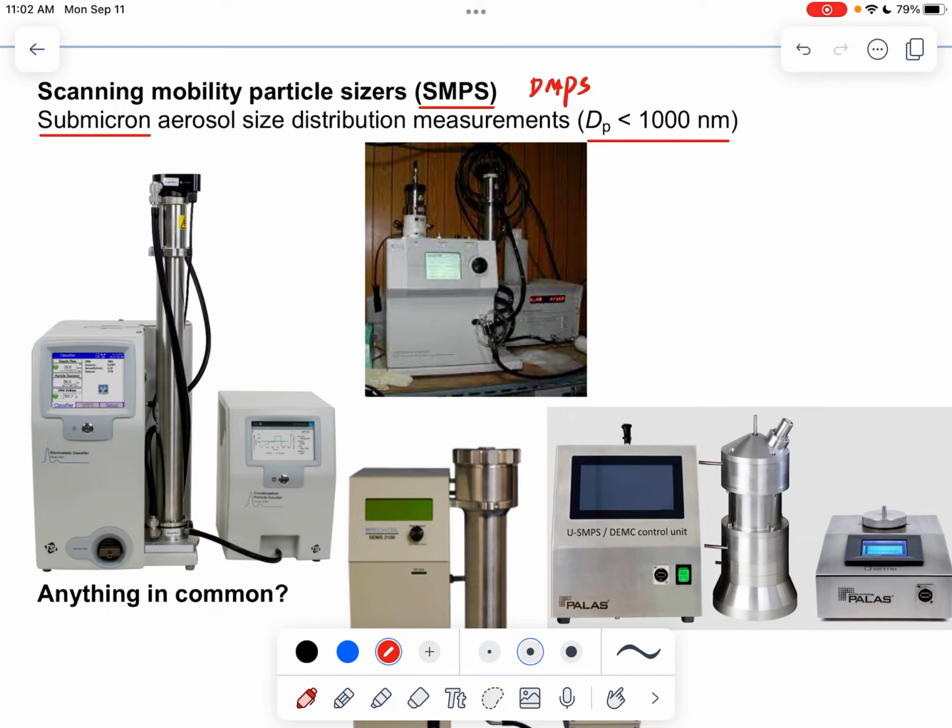the number of charges eventually carried by these particles is fixed. So there will be a certain percentage, let's say F1, of particles carrying +1, a certain percentage F2 carrying +2, F-1 carrying -1 charge, F-2 carrying -2 charges. And then there's also a fraction of particles carrying 0 charges, right? So the neutralizer neutralizes the ions on the particles so that they carry a constant charge distribution.